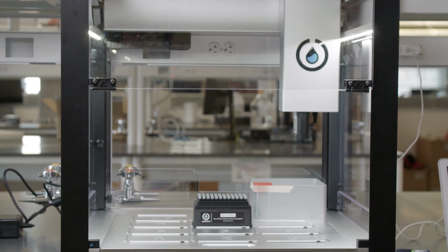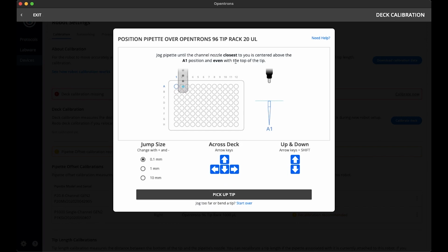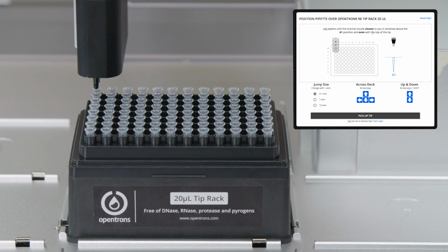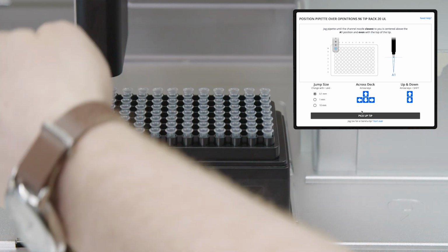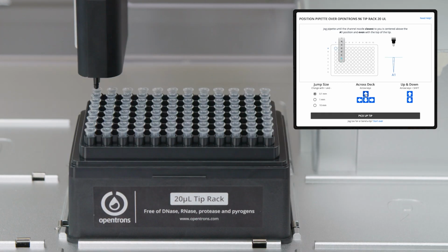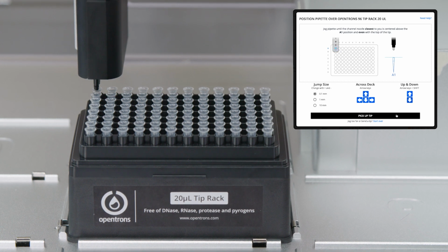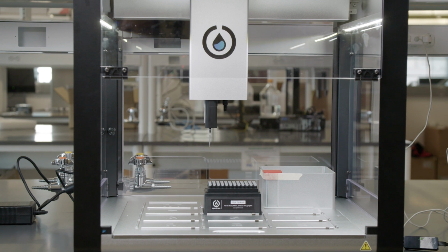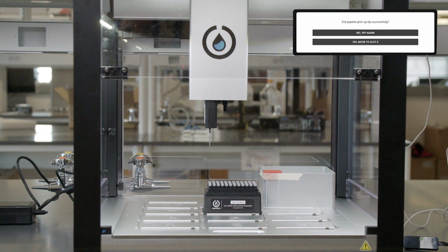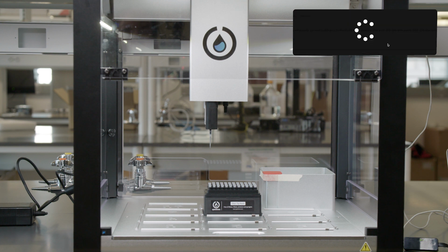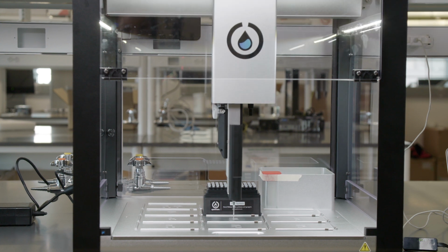On the screen, I have the ability to jog the pipette in the X, Y, and Z axis. I'll do that now so that the nozzle is centered in tip A1. The nozzle is now centered over tip A1, so I will now have the pipette pick up the tip. In the app, it asked me if the pipette did pick up the tip successfully. So I will select yes, and the pipette will move to slot 5.